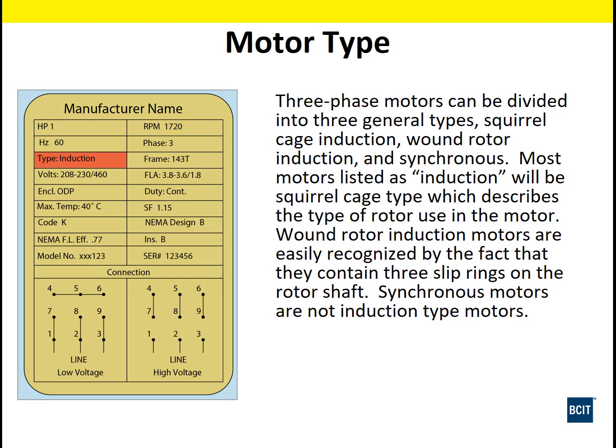Type of motor, induction or not. We know the wound rotor motor and the squirrel cage motors are induction motors. Synchronous motors are not. If it's a synchronous motor, it would say synchronous there. And DC motors, again, have a slightly different nameplate, but it would say DC motor there.